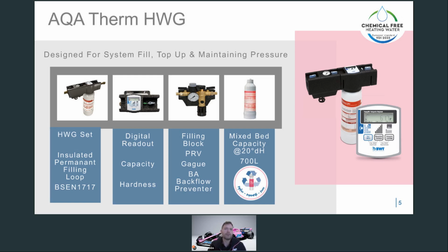The filling block has a pressure reducing valve and a pressure gauge to maintain desired pressure, as well as a BA valve, giving double protection against any backflow, which is directed to a tun dish. For added security, there's also a triple ball valve configuration, enabling you to manually isolate the water at multiple points. This system is controlled by an easy to use interface, monitored digitally and designed to be easy to use. Just set the parameters correctly and it's pretty foolproof.